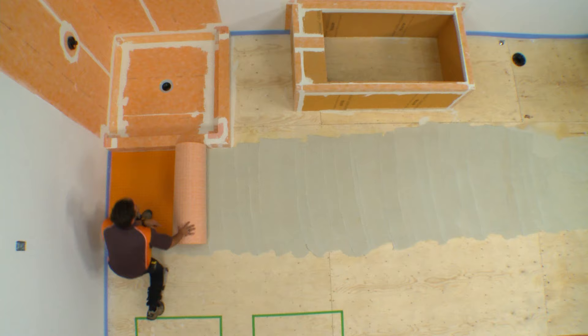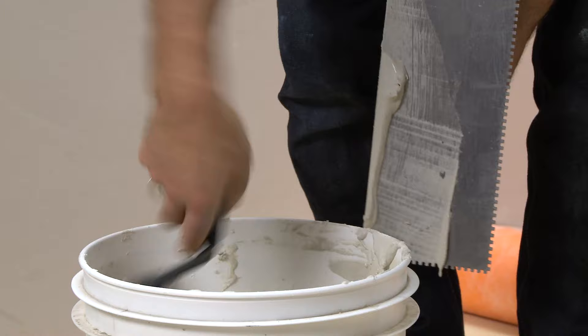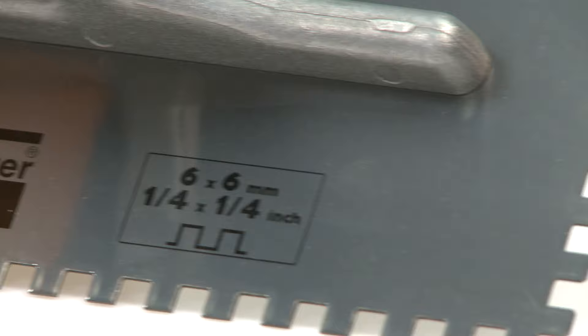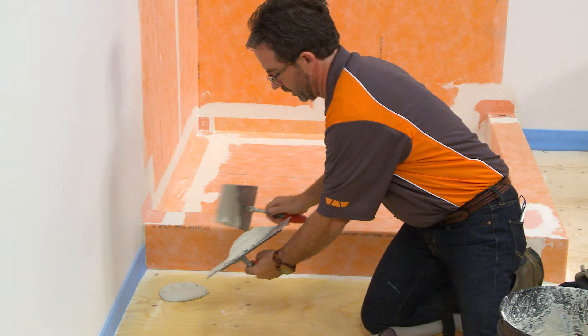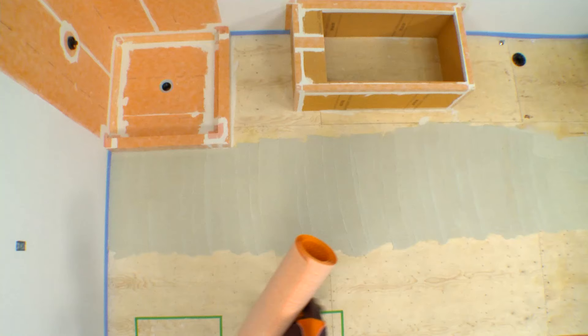DITRA-HEAT is installed simply and easily with thin-set mortar. We will use Schluter All-Set Modified Thinset Mortar to bond the matting to the wood substrate. Schluter Fast-Set Rapid Setting Modified Thinset Mortar may be used as well. If you are not using a Schluter mortar, a modified thinset mortar is used to install the matting over wood. The mortar is mixed to a fairly fluid consistency but still able to hold a notch. A ¼ inch by ¼ inch square notch trowel or the Schluter DITRA-HEAT DITRA XL trowel is used to apply the mortar. Apply a thin layer of mortar with the flat side of the trowel to produce solid contact with the substrate, and then comb additional mortar using the notch side.